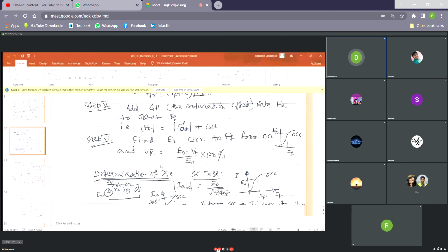You can use any standard low resistance or very low resistance measurement method, and then multiply the values obtained by this Kelvin double bridge by some factor, because there you use DC supply and the machine is actually used under AC, right? And there are skin effects, because of the higher diameter of the conductors, so the skin effect can become significant.